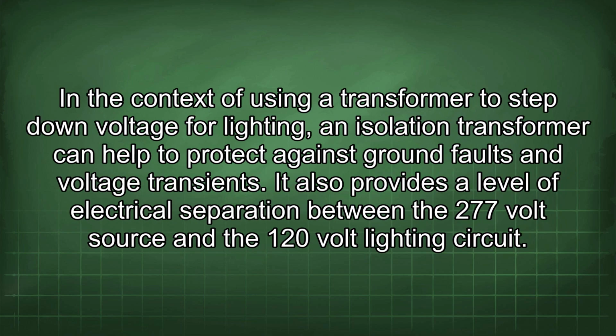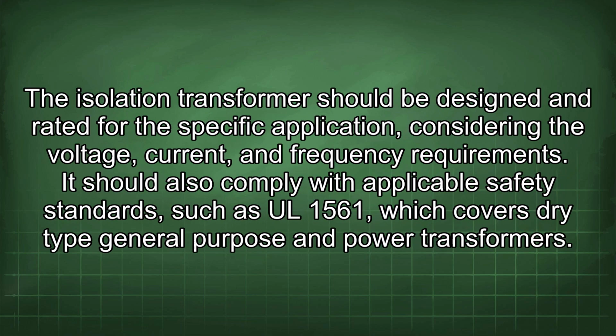In the context of using a transformer to step down voltage for lighting, an isolation transformer can help to protect against ground faults and voltage transients. It also provides a level of electrical separation between the 277-volt source and the 120-volt lighting circuit. The isolation transformer should be designed and rated for the specific application, considering the voltage, current, and frequency requirements. It should also comply with applicable safety standards such as UL 1561, which covers dry-type general-purpose and power transformers.